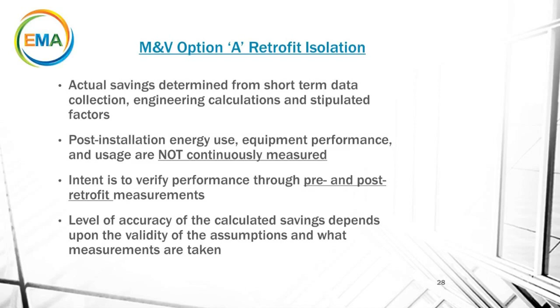Most of us are familiar with lighting upgrades. Now, this is an Option A example. Keep the number of fixtures, how much power is consumed per the existing fixture, what's our baseline, right? That's already installed. I'm going to change this out with a new fixture, the retrofit project. So how much is the new fixture going to consume? How many operating hours are we using that for, either way? We're going to keep them the same, apples to apples. And the energy savings is the difference between power consumed by the existing versus the new, multiplied by the operating hours. Total cost is the cost of the fixtures, furnish and install, with the labor to swap them out.